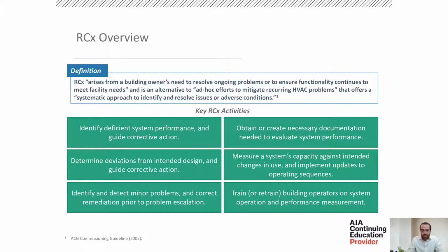Number 5, again added by us, is measuring a system's capacity against intended changes in use and implementing updates to those operating sequences. The example that comes to mind is changing many patient rooms to negative airflow for COVID or other considerations, or increasing OR air changes because of increased requirements. Determining if the system has space to really do that in the field is something you're going to be doing in retro-commissioning.